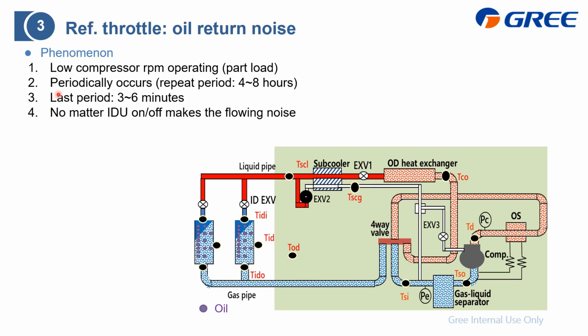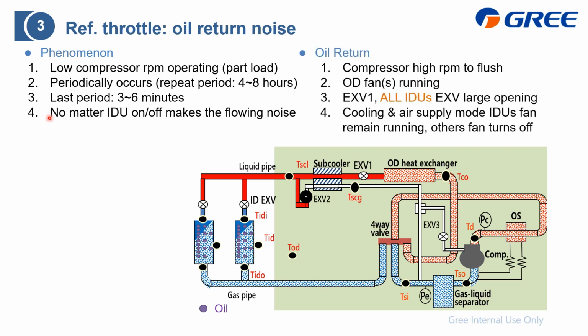And the second part is that it occurs periodically, which means it can repeat but the period is not fixed. About every 4 to 8 hours it will come out again, and the last period is about 3 to 6 minutes. This is for the oil return. And the last is that no matter whether the indoor unit is turned on or turned off, it will make the noise. And then next we will talk about why the VRF needs the oil return.